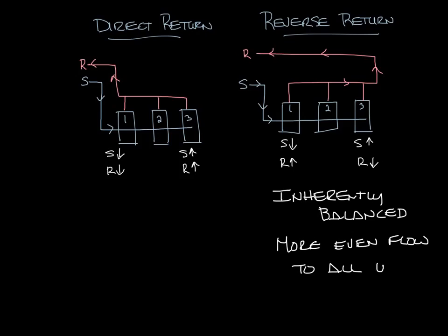You can see that the reverse return has a longer path so the direct return will have less piping which will reduce your first cost. But the benefits of having the inherently balanced system can outweigh the additional cost of the extra piping so you need to do a complete cost analysis.